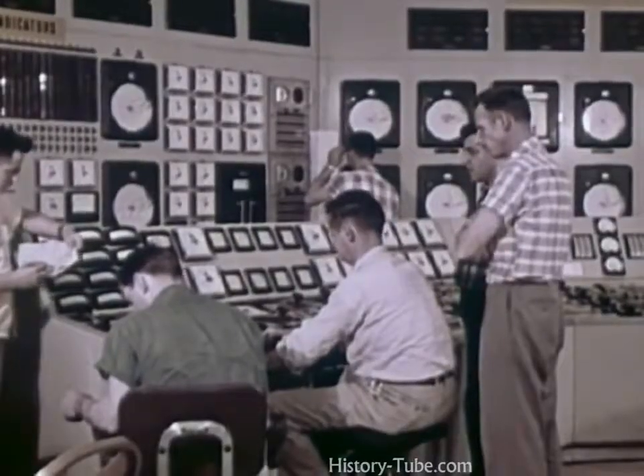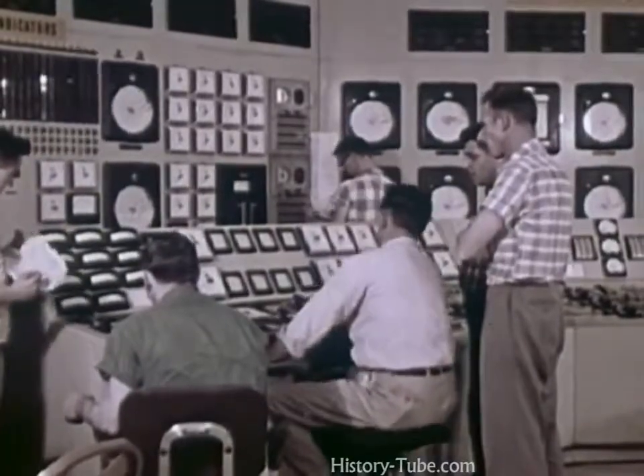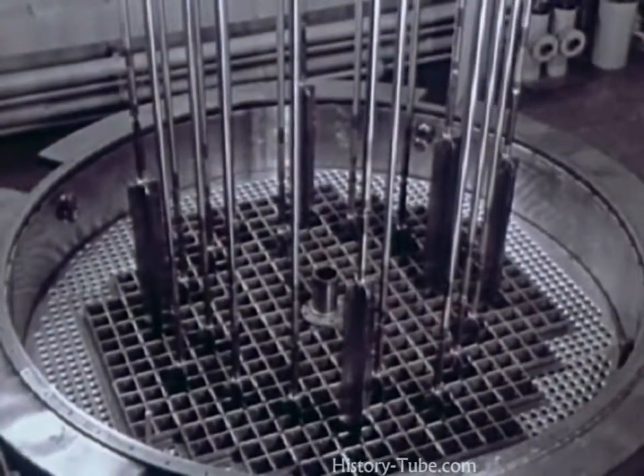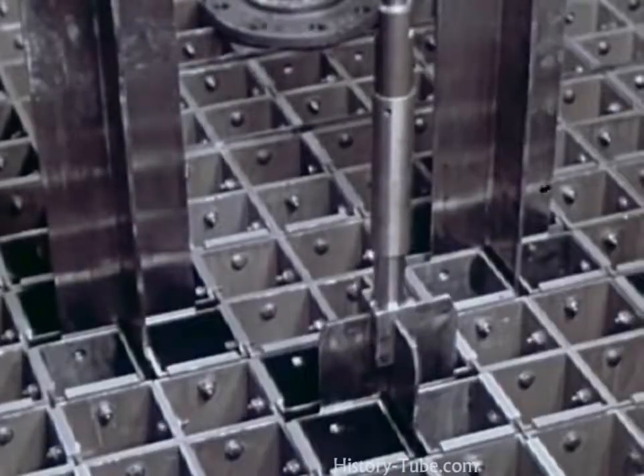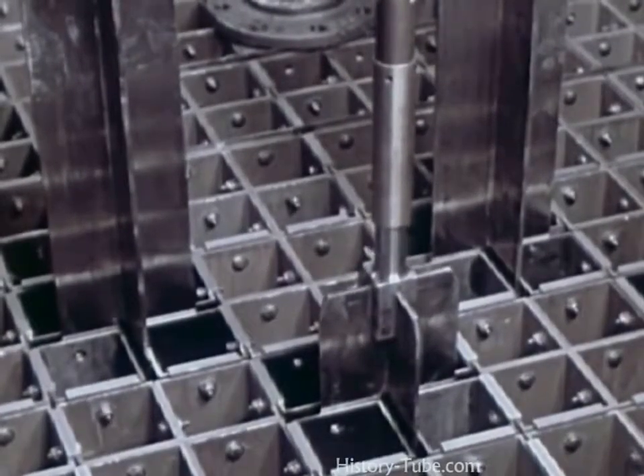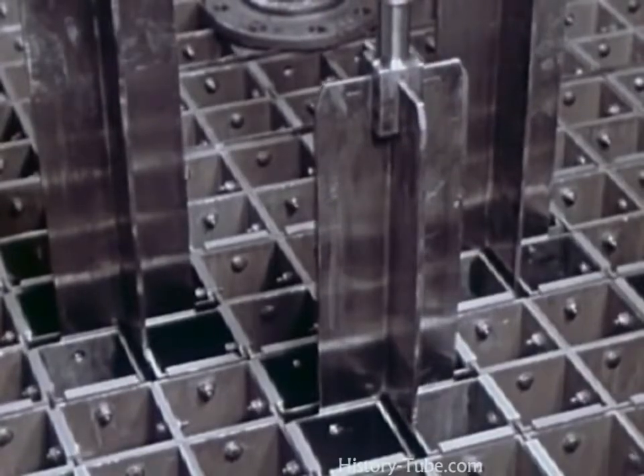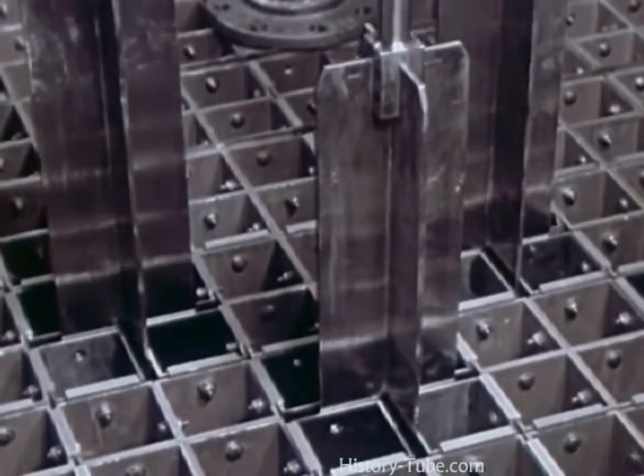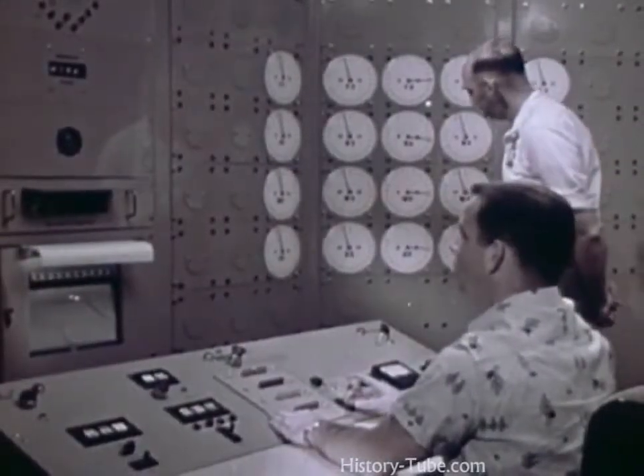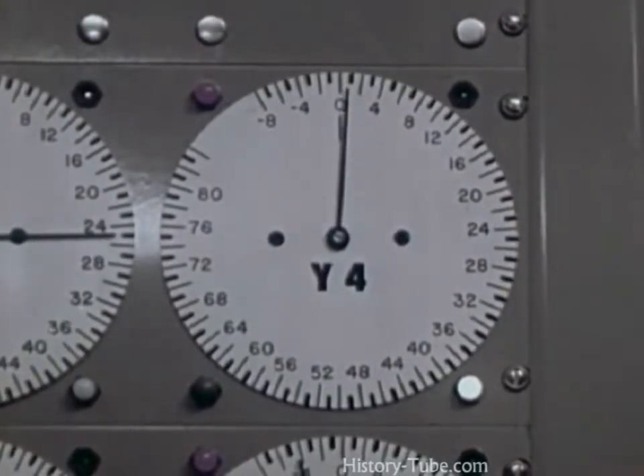Operating measurements that have been made in the plant indicate that the reactivity calculations were substantially correct, and that the 5% design margin that was included can be used to provide additional lifetime for the core. The critical assembly also permitted an accurate determination of the control rod positions required to bring criticality. It was important that this be determined because in a power reactor, unlike an experimental reactor, the technique of adding fuel as a means of slowly approaching criticality is not practical. The preliminary experimental work done made it possible to predict the initial critical position of the control rods to within a fraction of an inch out of a total motion of 6 feet.